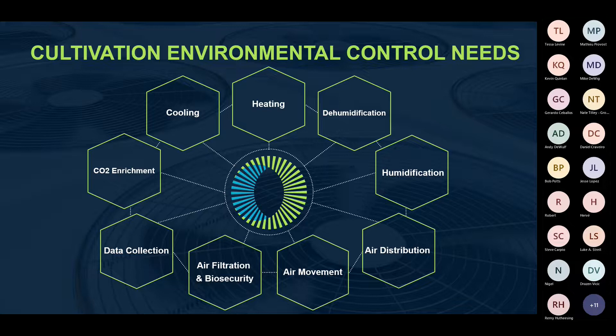On top of the large moisture removal requirement, these rooms also have a very dynamic load profile between lights-on and lights-off periods, and from the beginning stages of vegetative growth to the end of the flowering cycle. For the flowering cycles, which dominate the facility's space needs, the load completely flips 180 degrees every 12 hours. There's a concept from part one worth repeating: the productivity of an indoor cultivation facility is determined by its greatest limiting factor, or its most underperforming system. In our experience, the greatest limiting factor for most indoor facilities today is their mechanical systems — their ability to control temperature and humidity. The improvement of mechanical systems presents the greatest opportunity to maximize productivity for indoor cultivation businesses. This is exactly why Inspire was founded — to develop and deliver purpose-built systems and controls that are assets for growers, not a liability.